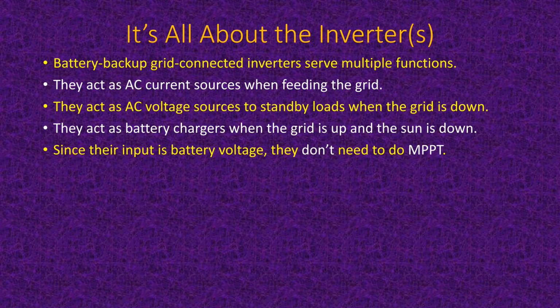But if the grid goes away and you've got standby loads to power, then you can't do that anymore. So you need to switch functions with this inverter, and it has to now act as a voltage source. So that's the key. Current source when the grid is up, voltage source when the grid is down. And if your inverter doesn't do that, it's not going to work for you in a battery backup configuration for a grid connected system. Okay, they can also charge the batteries when the grid is up and when the sun is down. So if at night your batteries are low and the grid is still there, they can charge them up.